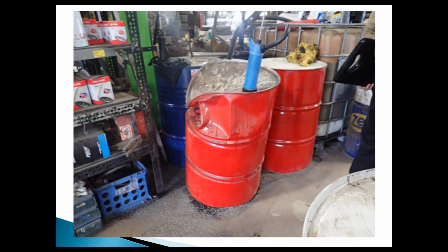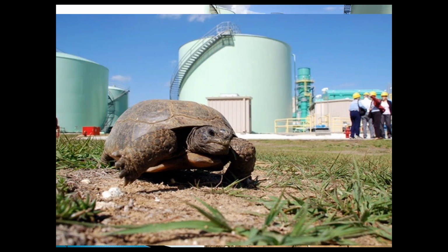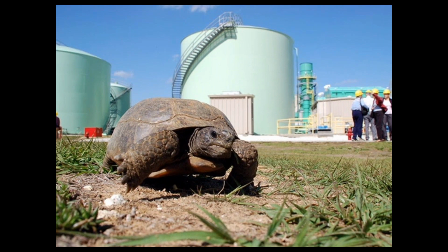This is just interesting because of this inspection. We looked at their inspection record and they kept inspecting this thing, saying it was damaged, but never did anything to fix it. And then this one's bizarre. You'll never believe it. With earthen materials, critters love to dig into those earthen materials. And in this case, you won't believe it, it was a turtle. But we find holes in containment all the time from burrowing animals, and it's a real thing.